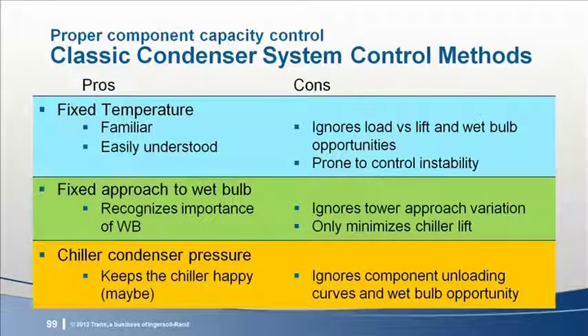A second shortcoming of each of these control methods is that they don't provide a clear path to coordinated operation of multiple competing components. In the case of a condenser water system, that would mean energy investment in the cooling tower fan versus the condenser water pump. However, these methods do have one huge strength. That is, operators are familiar with them and they at least think they can relatively quickly and easily troubleshoot them.